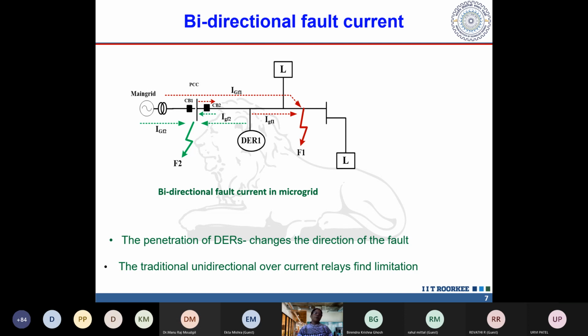So this relay location will see a fault current from left to right, or upstream to downstream. Generally, the grid side is denoted as the upstream side, and the downstream means the load side mostly, and of course the renewable sources side also. That's the downstream side. So if any fault occurs in this bus bar of the PCC, let us say F2, again the renewables will also supply a fault current, but it is in the reverse direction. So this relay R1 will see two currents for different fault positions, upstream to downstream, and then downstream to upstream. This is known as bidirectional fault current, and it creates problems for many relays, digital relays.